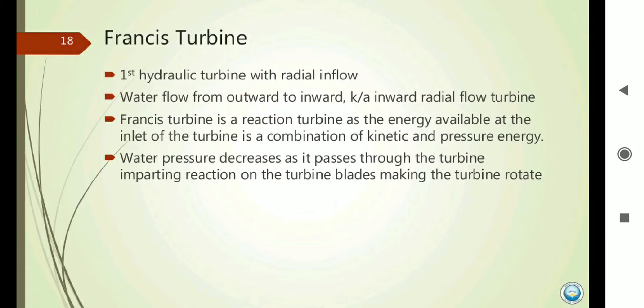Today we are going to discuss about the Francis Turbine. It is the first type of radial flow turbine. Water flows from the outward to inward. Francis Turbine is our first reaction turbine — a turbine where the pressure changes at the blade and also the nozzle. The energy at the inlet is a combination of kinetic and pressure energy. Water pressure decreases as it passes through the turbine, imparting reaction to the turbine blades and making the turbine rotate.